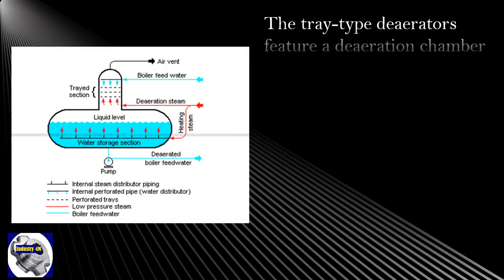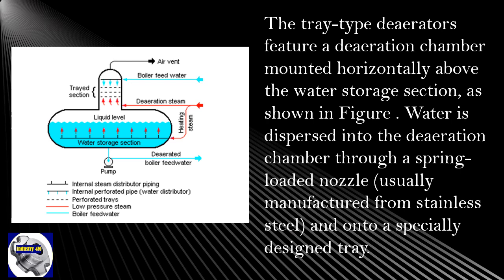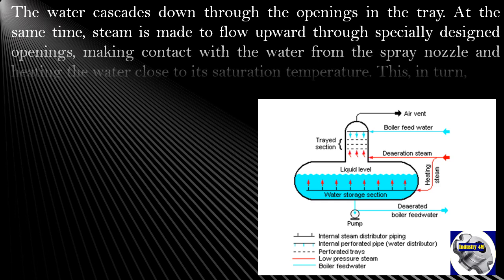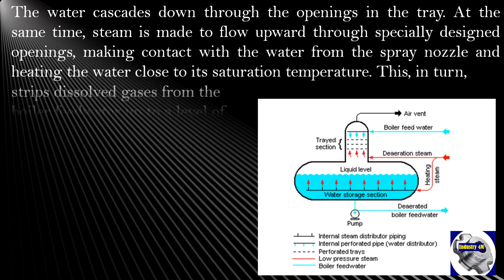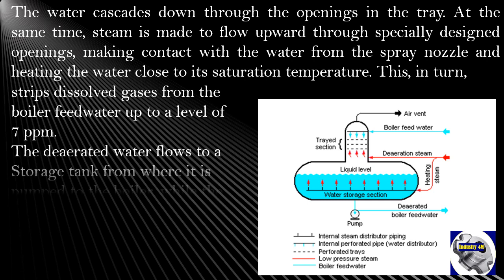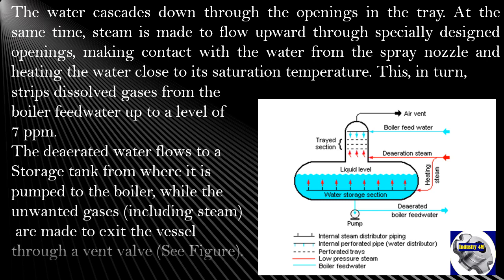Tray-type deaerators feature a deaeration chamber mounted horizontally above the water storage section, as shown in the figure. Water is dispersed into the deaeration chamber through a spring-loaded nozzle, usually manufactured from stainless steel, and onto a specially designed tray. The water cascades down through the openings in the tray. At the same time, steam flows upward through specially designed openings, making contact with the water from the spray nozzle and heating the water close to its saturation temperature. This strips dissolved gases from the boiler feed water to a level of 7 parts per million. The deaerated water flows to a storage tank from where it is pumped to the boiler, while the unwanted gases, including steam, exit the vessel through a vent valve.